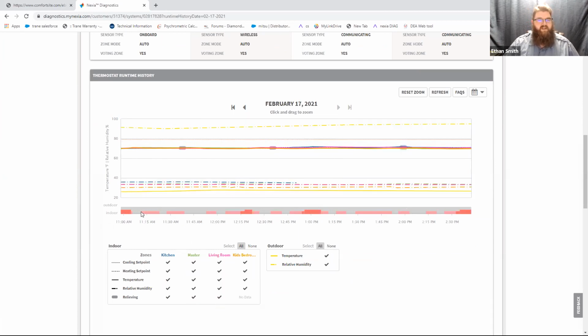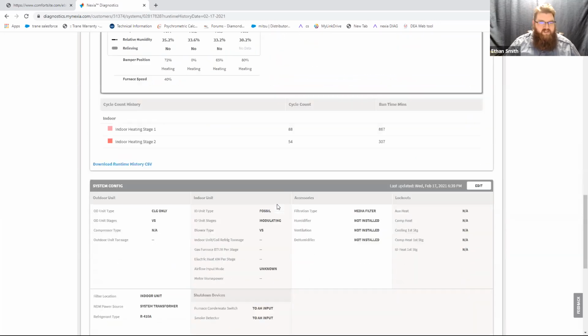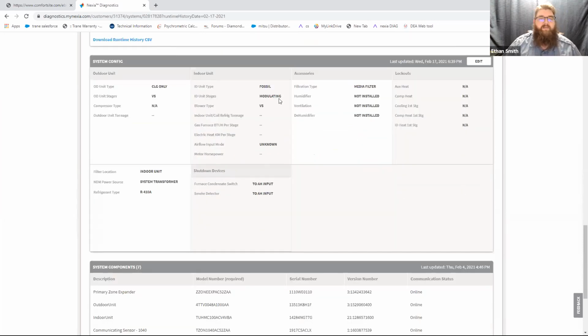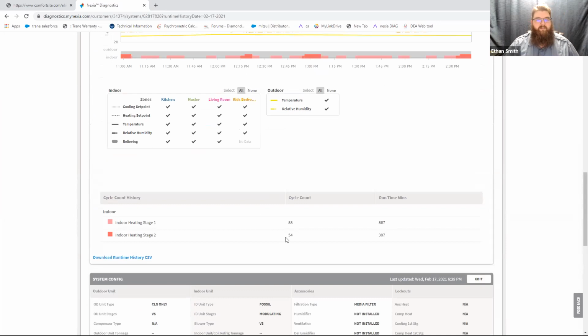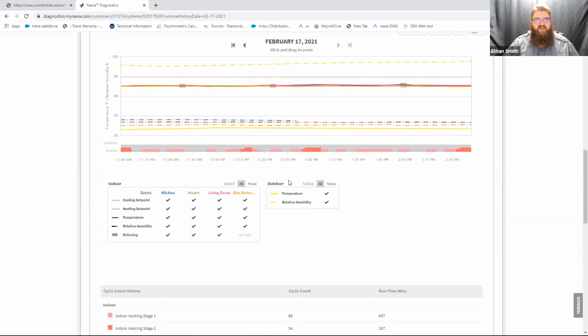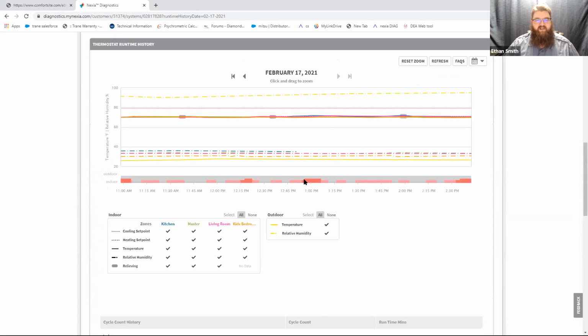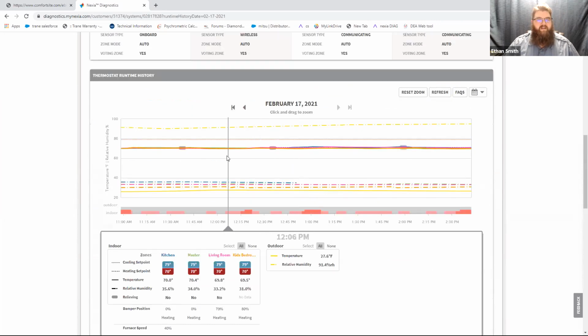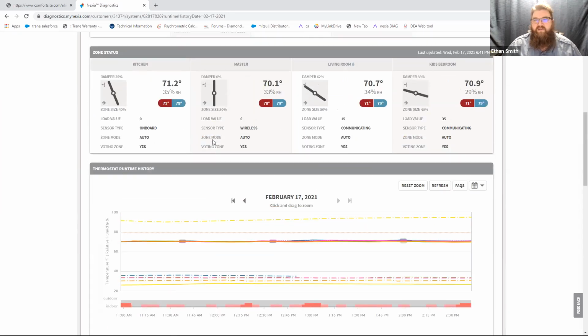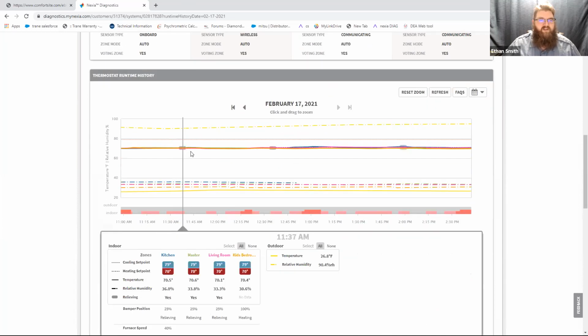So down here on the bottom, you can see where the furnace is in first stage versus modulating stages. I think he's got a modulating furnace. Let's check. Yeah, he's got a modulating furnace. So modulating range is anywhere inside stage 2. You'll notice we have several different levels of the dark red, and you can see in here these little bulged out spots. If I'm on one of those, it's calling for that kid's bedroom, which is kind of small, that zone size was only 35% or 40%. So it's a little small for the lowest stage furnace.